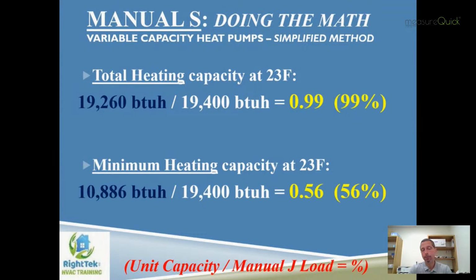And again, I know we're limited on time here, but many of you are probably used to Manual S, and you'll know that we're allowed to use airflow adjustments to help massage the output of that unit a little bit. So if we bump our target fan speed up a little bit, we can normally get about a 1 to 2% bump up in sensible heating output from a heat pump. So I feel pretty good in saying that that heat pump can meet 100% of the load.